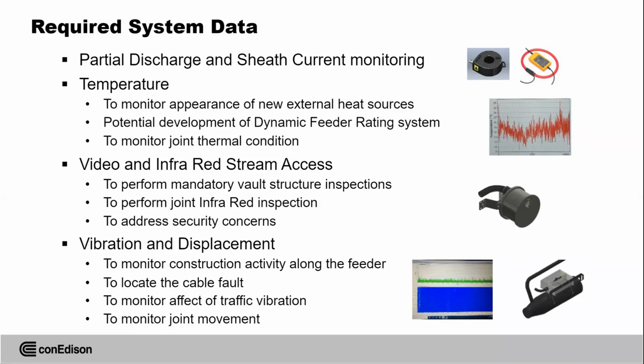If you have your baseline for your joints and terminations specifically, and if it's possible for your cable, you have a baseline when you energize the system, and then you can check it periodically every 5-6 years, or if you have an online system, you see it online: any change in behavior of partial discharge parameters, repetition rate, magnitude, and correlation with your major power signal. If one of these parameters changes, it can already give you an indication.